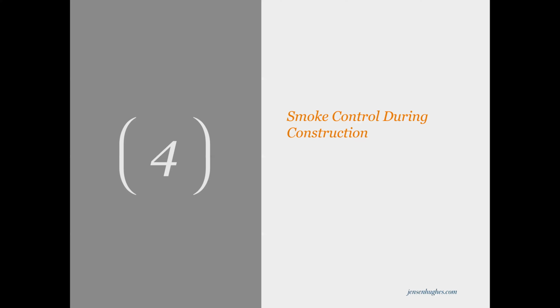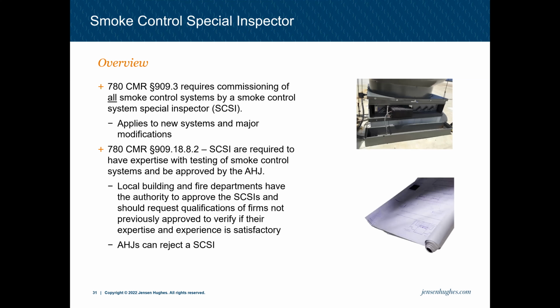So at this point, the project's hopefully gone through the permitting process and construction has started, and that's when smoke control and most other things start to shift from the design phase to the construction phases, though the engineers of record still have some oversight. For smoke control, that is primarily smoke control special inspection. 780 CMR requires a commissioning of all smoke control systems to be done by a smoke control special inspector. And that applies to all new systems and major system modifications. That second term, major system modifications, is somewhat ambiguous for exactly what would constitute that. And some of that is based on what the AHJs are requiring or requesting.